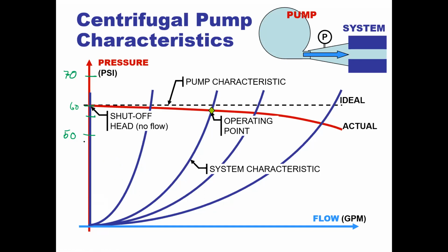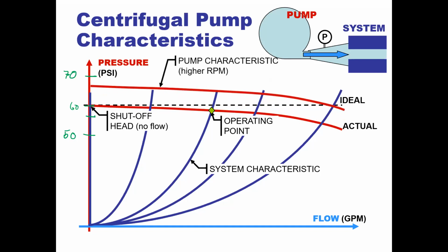Remember, this entire time we've been messing with the system characteristic. We have not touched the pump characteristic. And changing out the pump may not be an option. But if we run it at a different RPM, whether an increased RPM or a decreased RPM, we will get a drastic change in pressure.